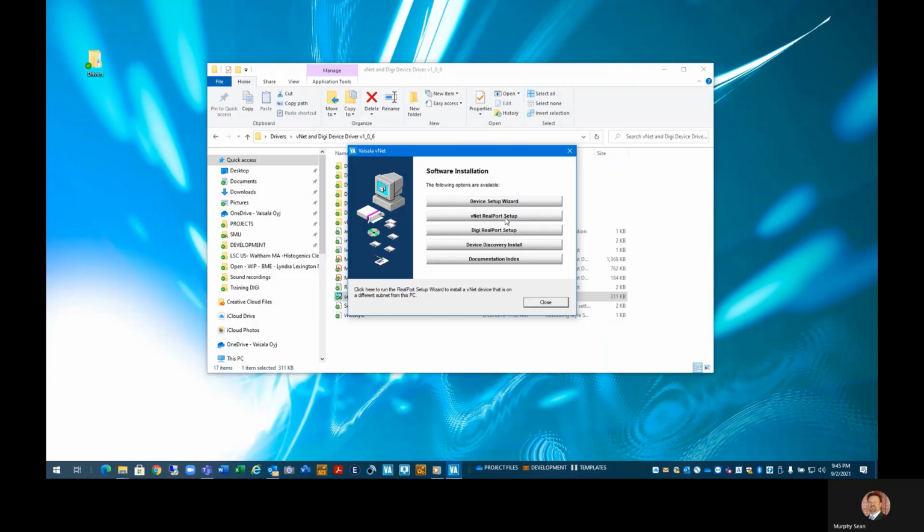One is to install a DIGI device install. This is a program that's good if you, let's say, have a small demo system with 3 or 4 devices, and your server and your hardware are all on the same subnet. So in other words, it's almost like a home network kind of situation where everything is all clustered together. It's not a typical viewLinc system where the server is located on a VM offsite. You would never really use this except for demo purposes. The other one is the device setup wizard. You typically don't use that, and there's additional documentation that's buried in here.